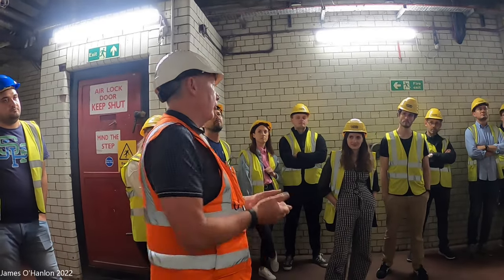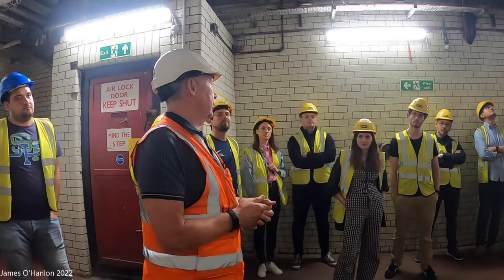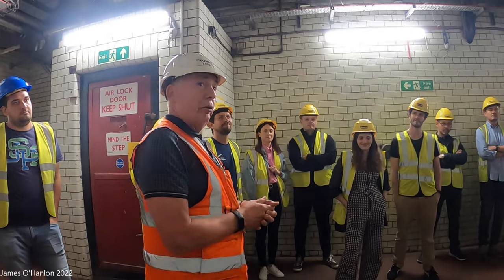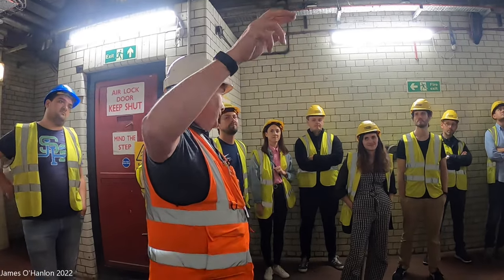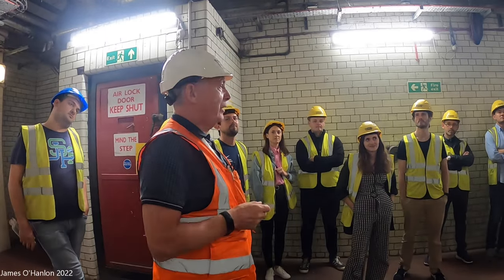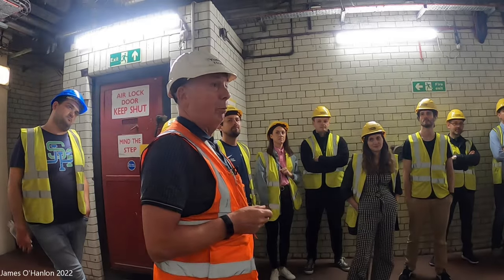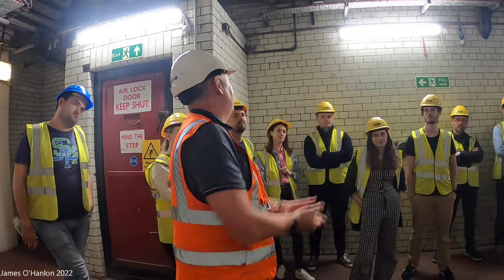But of course, they didn't know a lot about the combustion engine, didn't know a lot about carbon monoxide, so they didn't know what to give us. So what they did, they over-engineered everything. So these fans, as Alison said, are 28 feet in diameter, 25 tonnes in weight, with a top speed of about 68 to 70 revs per minute. They're not built for speed, they're built for pulling power in this case, and the exhaust is built for sucking power.